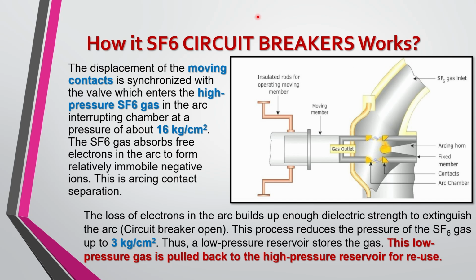Let's proceed further. So how SF6 circuit breakers work has been shown in this picture. The displacement of the moving contacts, as you can see in this picture, there is a moving contact and there is a fixed contact. As you can see, these contacts are fixed contacts and these are moving contacts. So this is a moving member. This entire thing is in contact first with these fixed contacts, but as soon as the fault occurs, this entire thing is pulled back in this direction, left direction, and the whole thing is disconnected. The whole moving member comes back and this is disconnected.